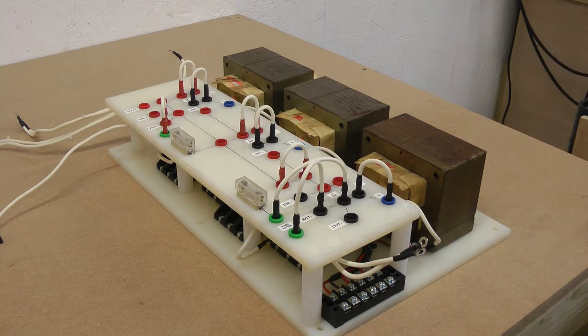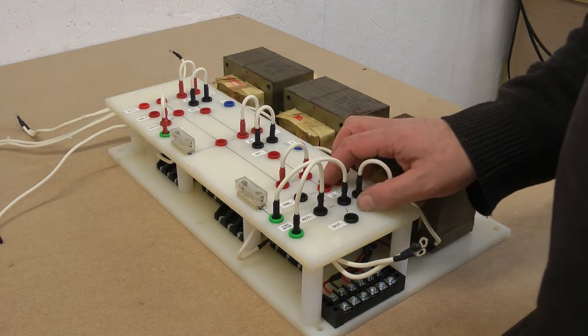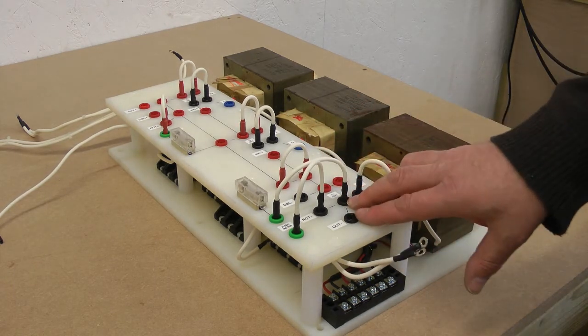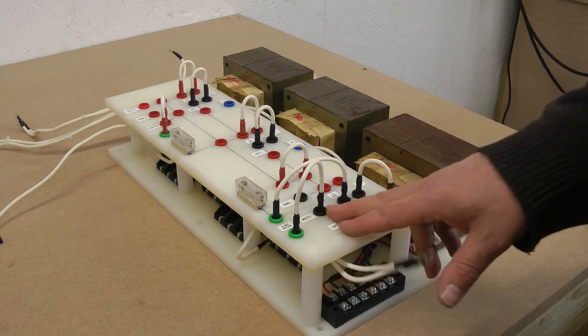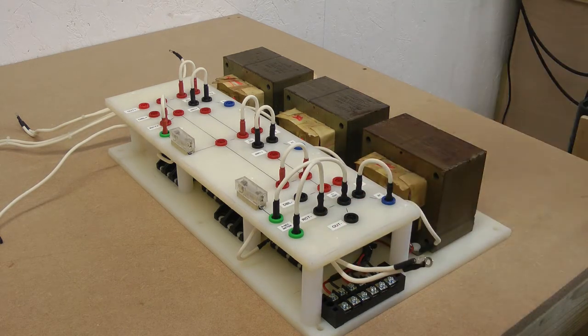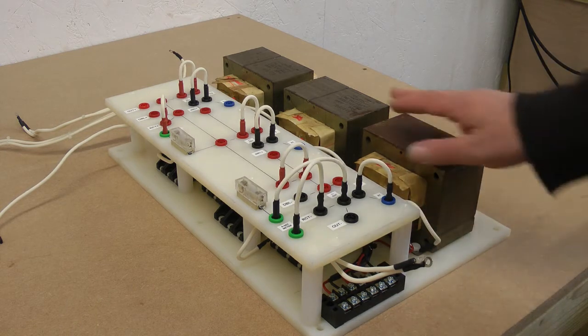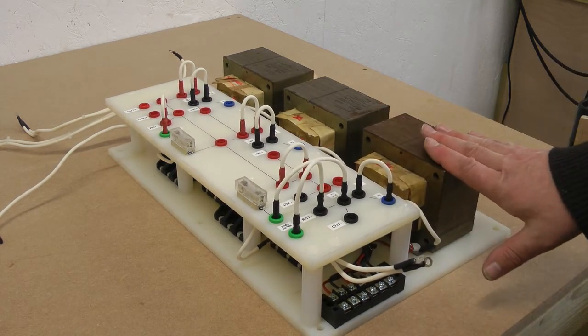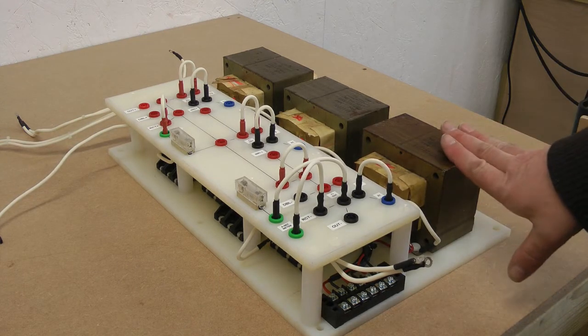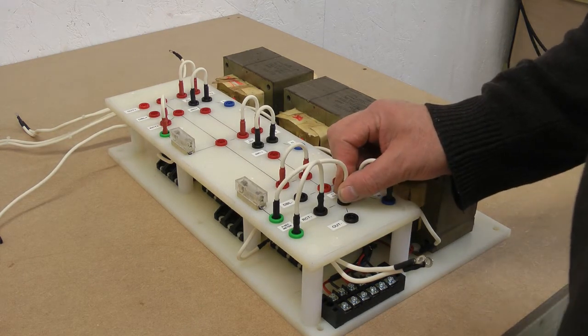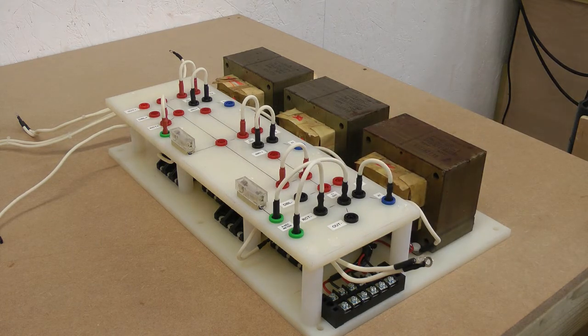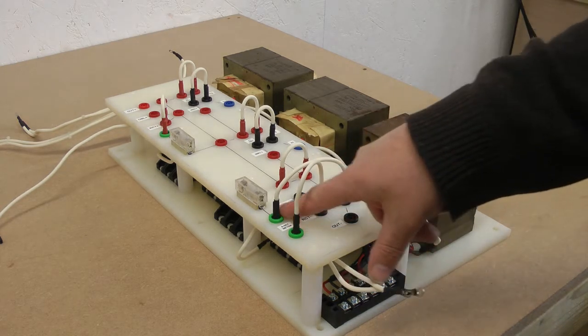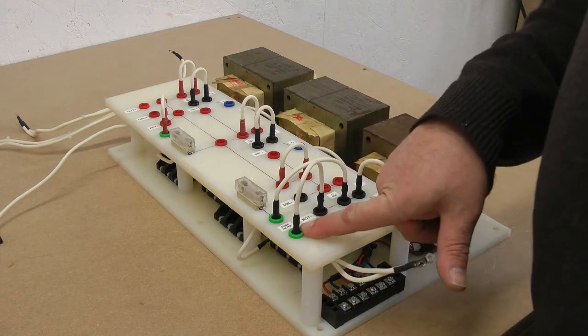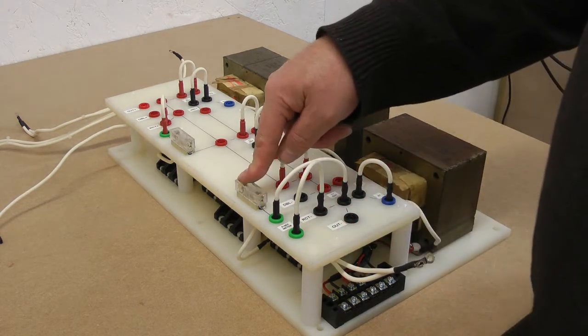So the outputs, if we look at one transformer here, the negative side of the output of the transformer, which is essentially the core here, is held down to transformer earth and can also be connected from transformer earth to line earth. So this is actually an earthed core in this configuration. The negative side is where we've got the secondary current, so it's marked A secondary, ASEC, on the front panel, and these two green terminals are for that meter. And it incorporates a fuse as well.